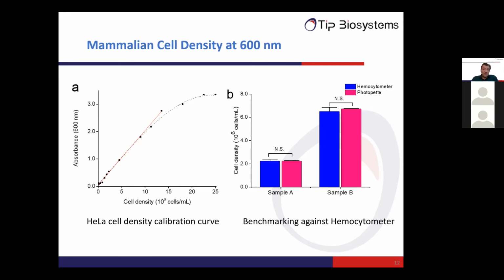So this is a very classical old-style method. It's very accurate, but it's very tedious. And we have calibrated the Photopette system against this method for many different types of mammalian cell lines. And those calibrations are inbuilt now in the device, which allows the user to do accurate measurements within seconds. And what you see here is the absorbance as a function of the cell density.